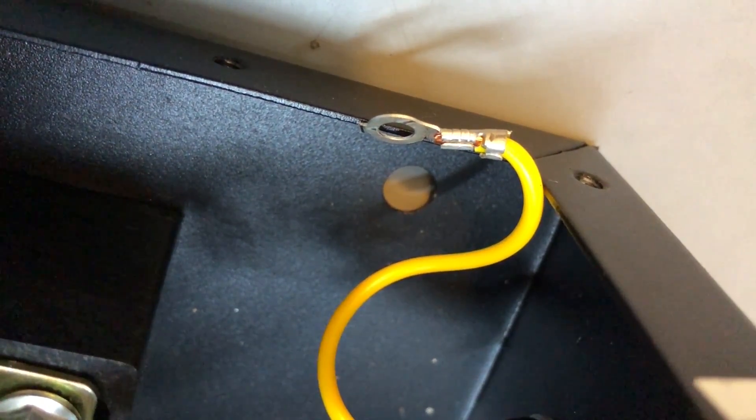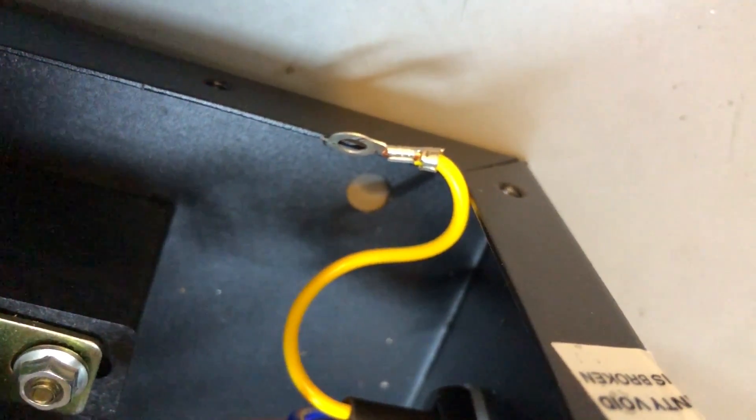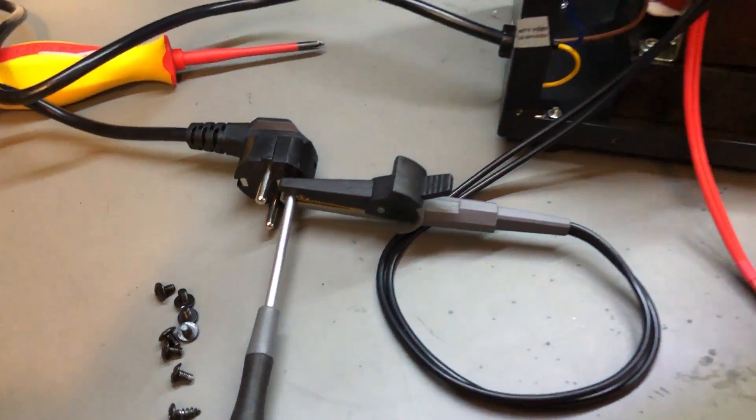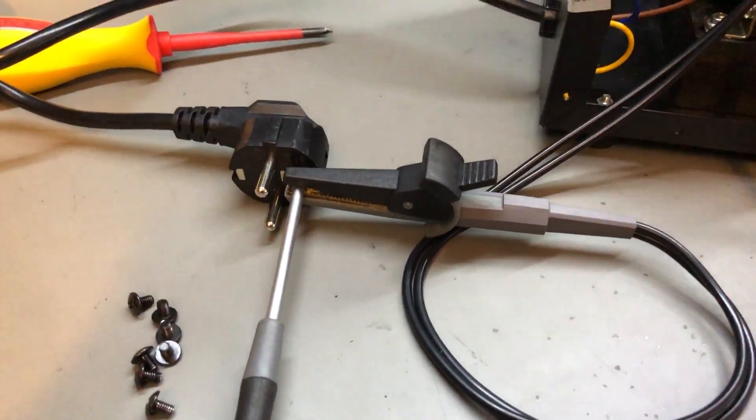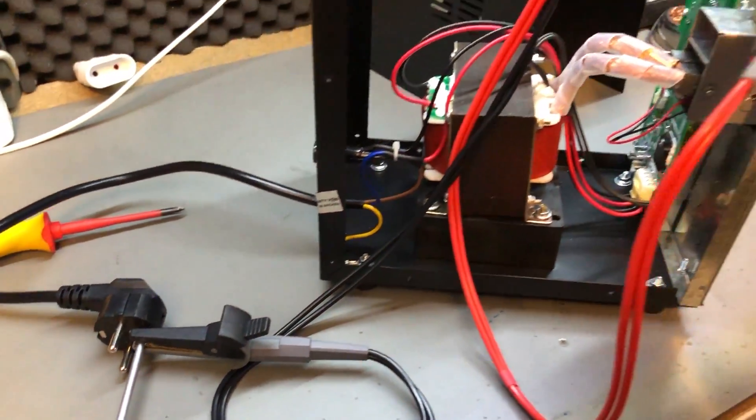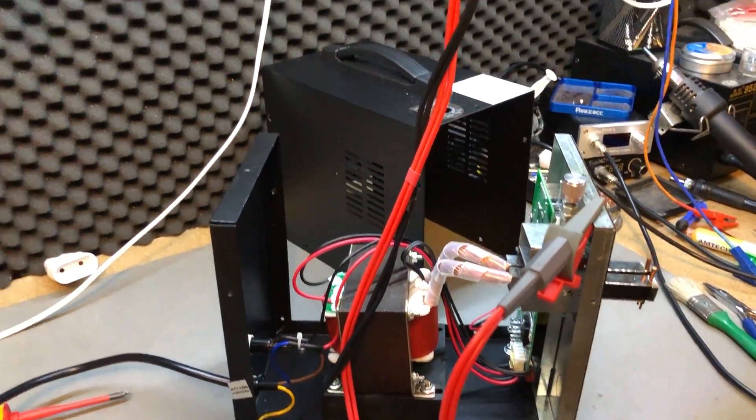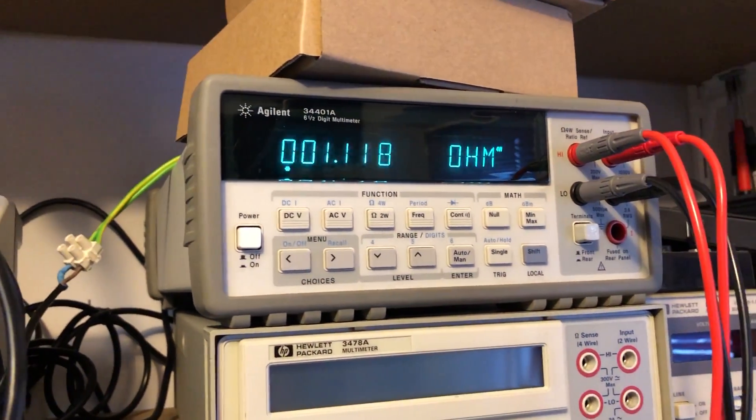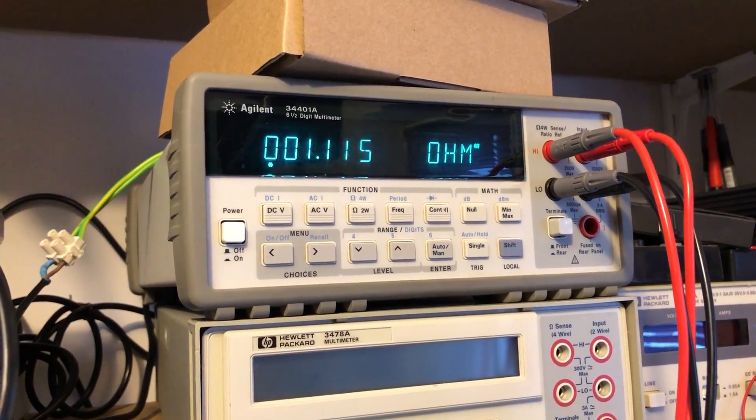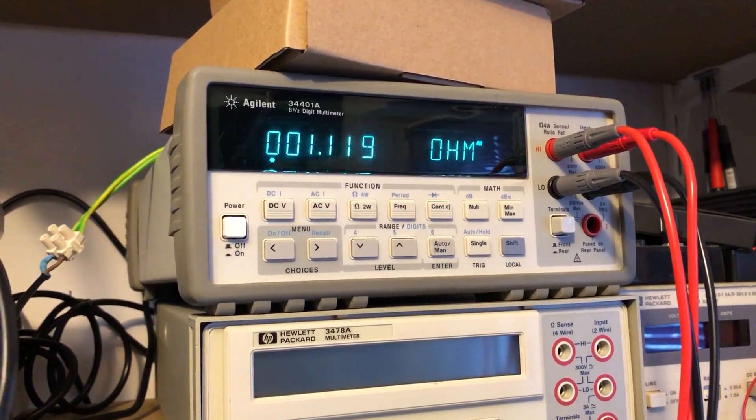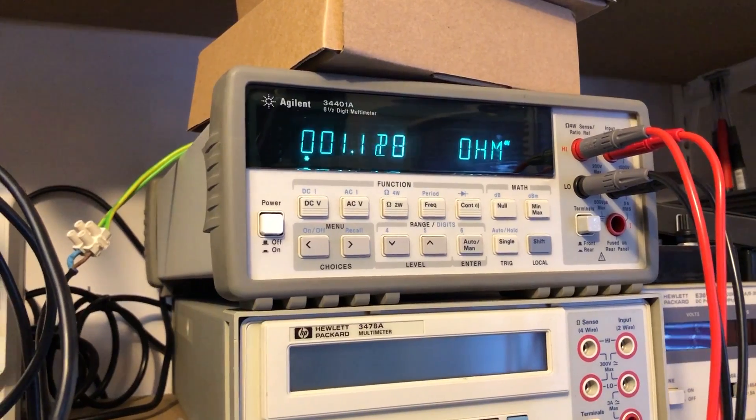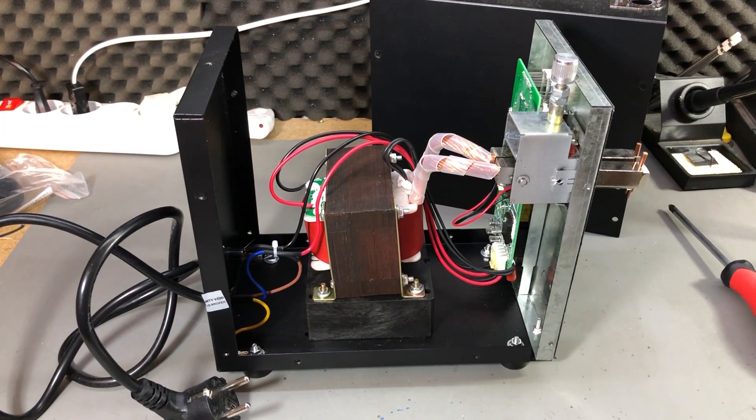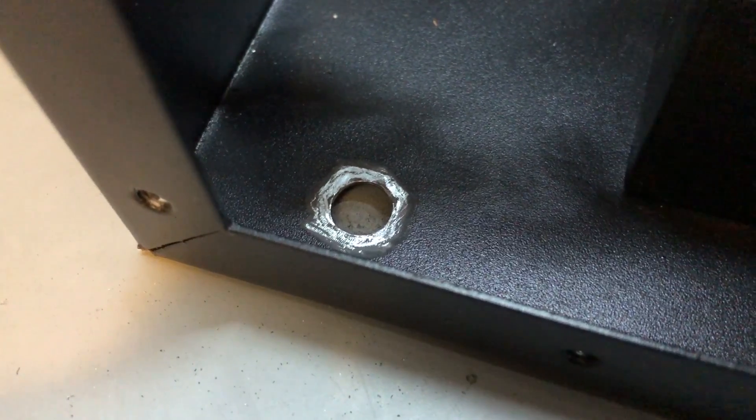I was surprised to find out that from the ground point to the end of the power cord all the way up to the metal chassis, I was measuring 1.1 ohms. I was expecting much worse because of all of that paint on the metal chassis and the improper contact but it was still a value of 1.1 ohms.